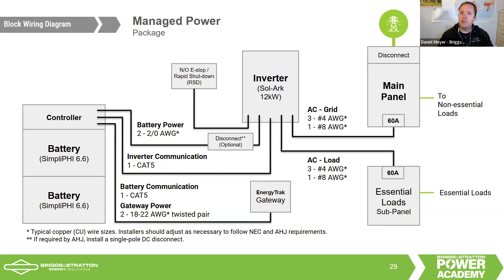Let's try not to imagine this, but picture that your house is on fire and the fire department shows up. What are they going to do first? They're going to kill power to your home. Usually they do that by either pulling the meter out of its socket or turning off the main breaker. But when you have a home energy storage system, as far as the solar and batteries are concerned, that's just another outage, and the inverter will start using energy stored in the batteries to power the home loads.